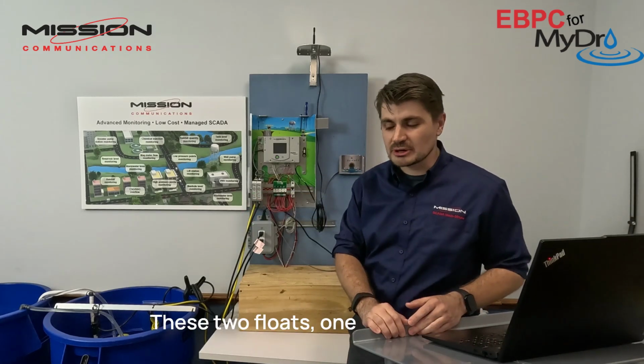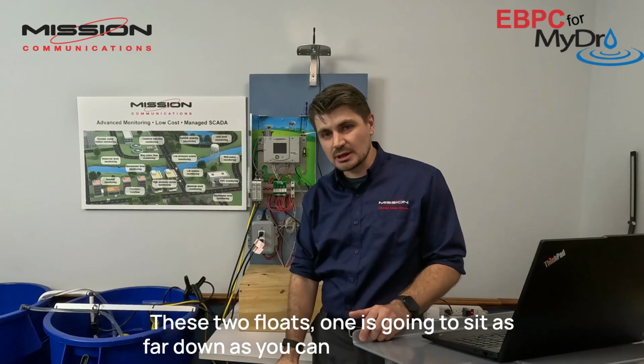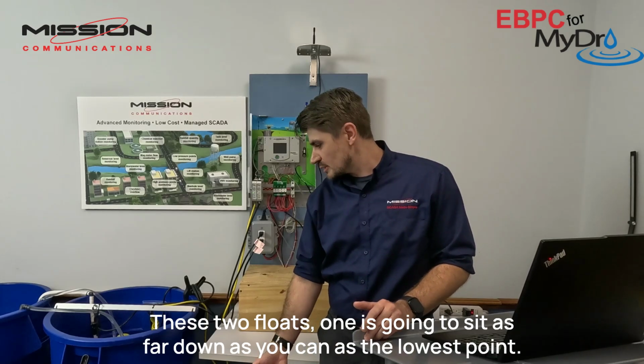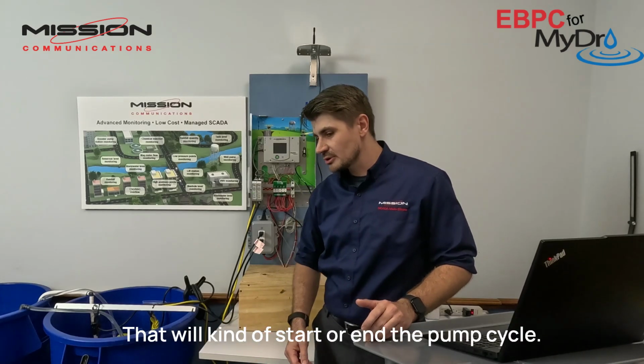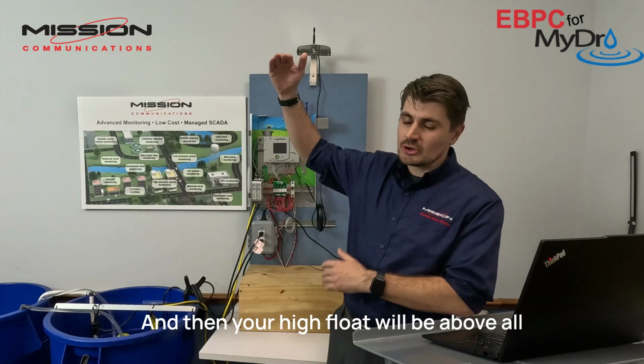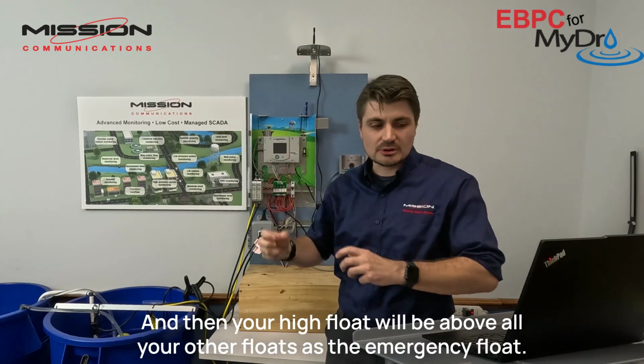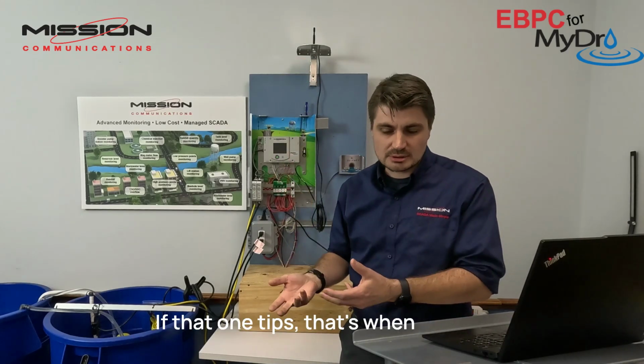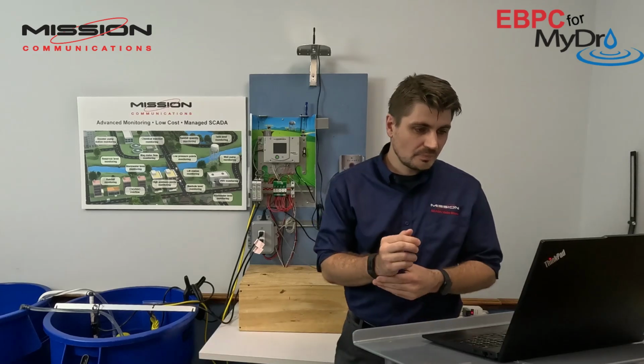These 2 floats, one is going to sit as far down as you can as the lowest point. That will start or end the pump cycle, and then your high float will be above all your other floats as the emergency float. If that one tips, that's when your pump controller has failed.